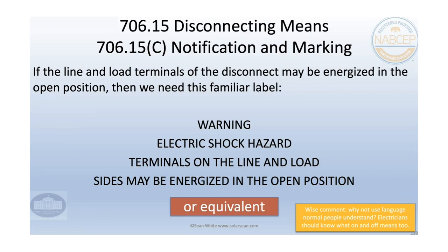I had a couple of people send me lists of questions. And so here is a famous sign that we see throughout all the renewable energy places. In the code, it's the one that says, warning, electric shock hazard, terminals on line and load sides may be energized in the open position. And so if you might have electricity on both sides after you turn it off, then you would put this sign there. And one of the places that I've seen people put this sign where they don't need it, I guess it's not going to hurt if they put it there though, is on an AC side of an interactive inverter. So you have an inverter that goes to the grid.